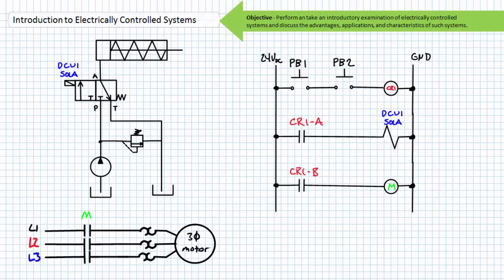If neither the cylinder extends nor the drill starts, my first point of inspection will be the common control system. If, however, the cylinder did not extend, yet the drill started to rotate, I would inspect the second rung of our ladder logic control system, or I would check our hydraulic power unit.